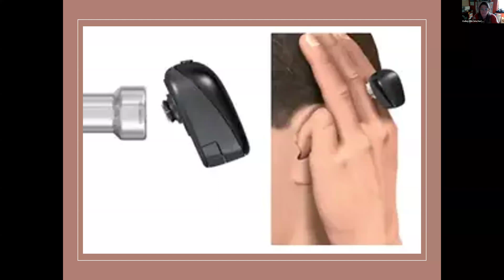Some of the biggest things that I see with BAHAs, particularly those on a soft band, which means the headbands, is that the soft band is not tight enough on the head. The rule of thumb: if you can fit 3 fingers between the headband and the head, and you can stretch it, it's way, way, way too loose. It needs to be tight enough so that the connector piece connecting the BAHA to the soft band is tight up against that bone, because a BAHA works through vibration. If it doesn't have tight enough contact with that bone, it's not going to vibrate as it should, and you're going to hear a lot of whistling.